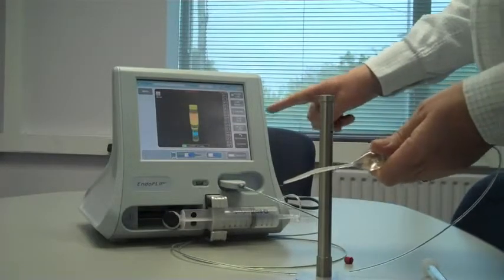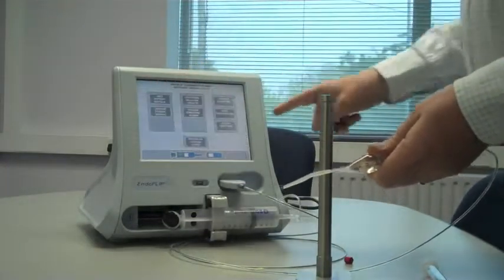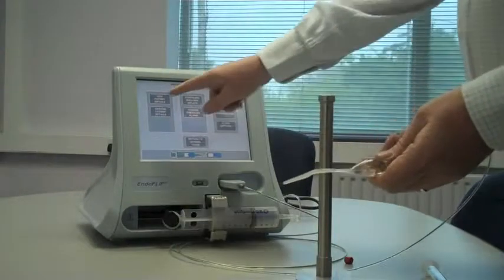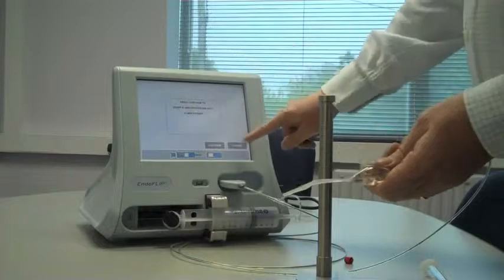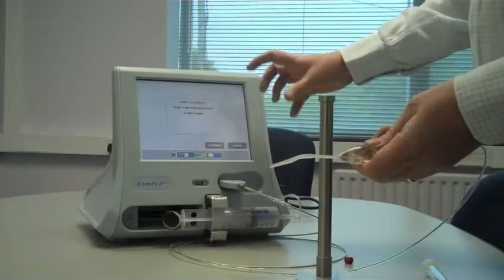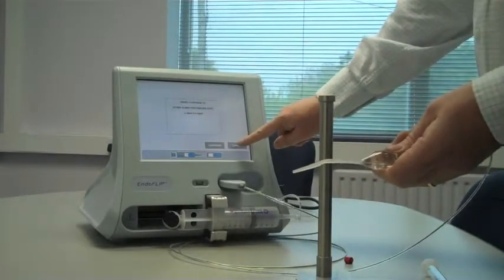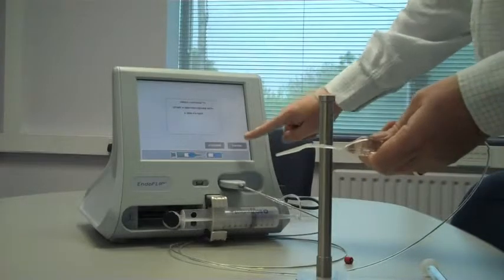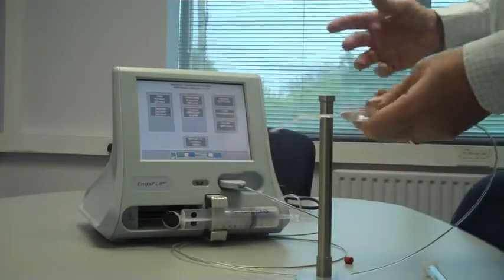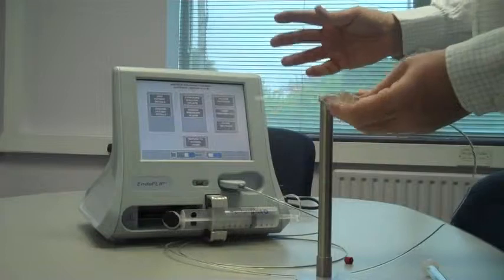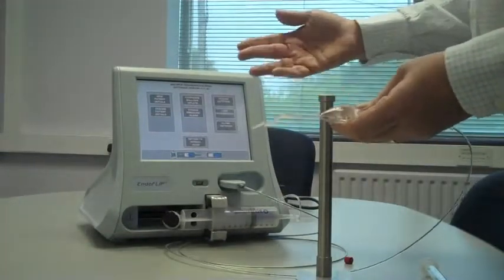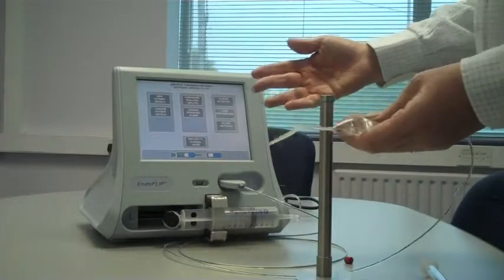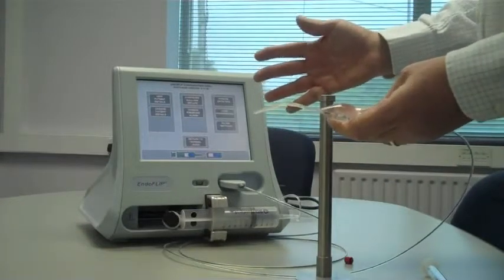I'd like to now take you through the menu. There's not too much in it. New patient details would be for a new patient, so we wouldn't use this here since we've set up the catheter. It's very important to note that when you enter a new patient, this is a single patient use catheter. You cannot enter a new patient details for the same catheter, so you only get to do that once.